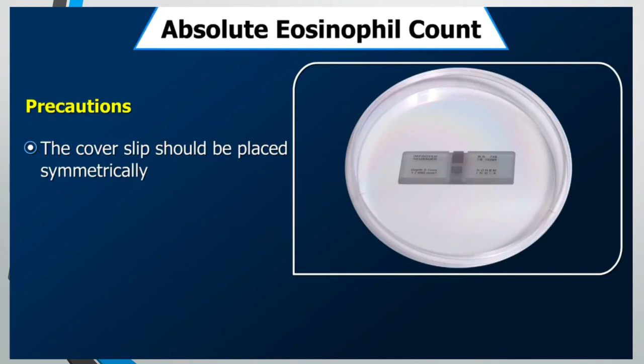Precautions. The prick should be bold enough to give free-flowing blood. At no stage should the finger be squeezed to take out the blood. Both the chamber and the cover slip should be dry and free from grease. Use only a dry pipette. Never use a broken cover slip. Before charging the chamber, the fluid from the stem of the pipette should be discarded. The cover slip should be placed symmetrically so as to cover the ruled area completely. There should be no under or overcharging of the chamber. The count will be low in both cases.